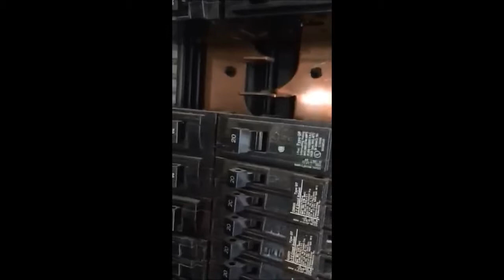Another issue we find here, and this is pretty common, is we have a circuit breaker that has been double tapped. You might have heard of this term before, and that's when we are taking two wires and attaching them to one single circuit breaker. This is pretty common out in the field, but these circuit breakers are intended to carry one wire.